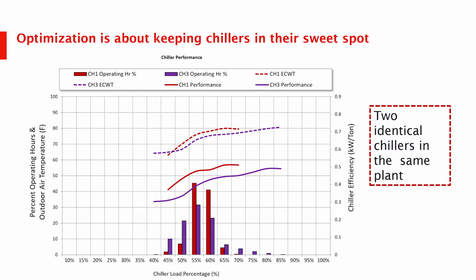Chillers consume the most energy and also drive the efficiency of the whole unit. I'm still surprised when I see identical systems - same chiller, same install date, same type, same operating conditions - and three years later, one is substantially less efficient than the other. That's not unique to chillers; it can be fans, it can be pumps. Something has happened in the time since that equipment was commissioned.